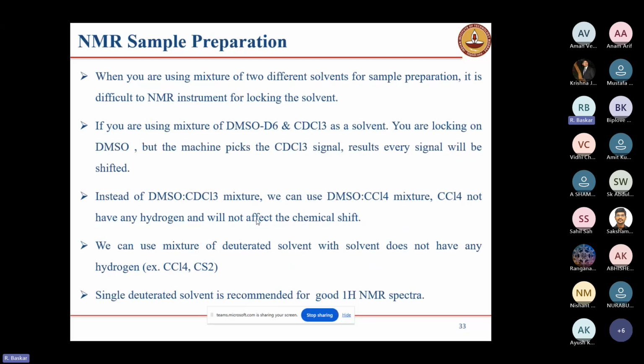When you are using a mixture of two different solvents for sample preparation, it is difficult for the NMR instrument to lock on the solvent. If you are using a mixture of DMSO D6 and CDCl3 as a solvent, you lock on DMSO, but the machine picks the CDCl3 signal. As a result, every signal will be shifted into the DMSO range. Instead of a DMSO and CDCl3 mixture, we can use DMSO and CCl4, because CCl4 does not contain any deuterium or hydrogen. So the shift will not happen, and we can easily use this kind of mixture. Instead of other deuterated solvents, I mean other non-protic solvents, we can also use CS2. But a single deuterated solvent is recommended for good proton NMR spectra.